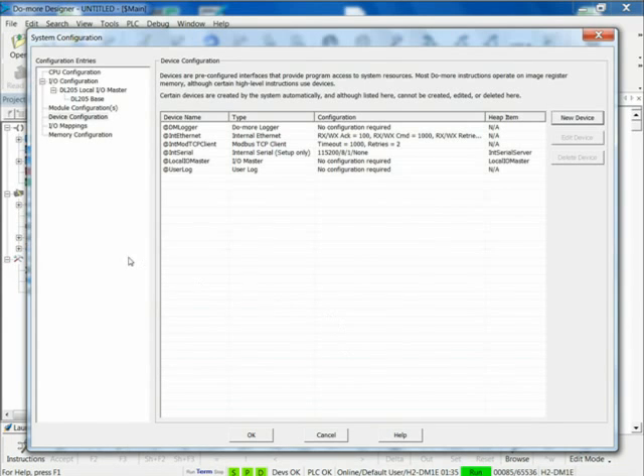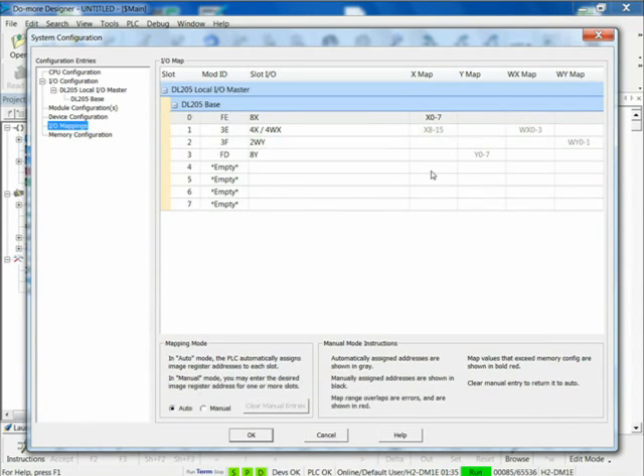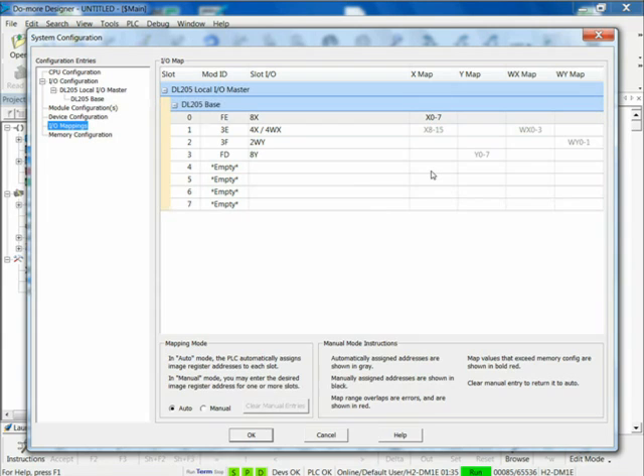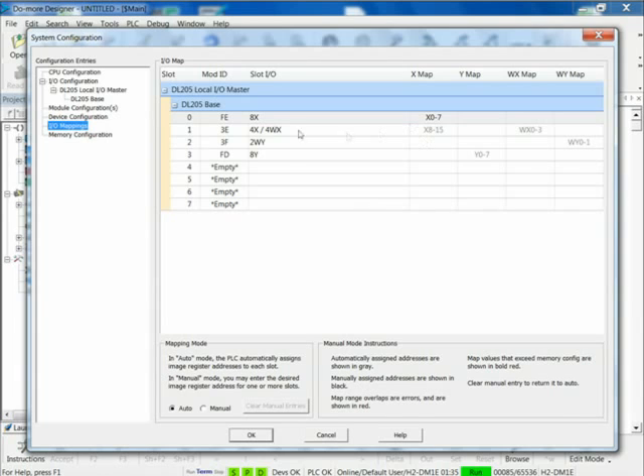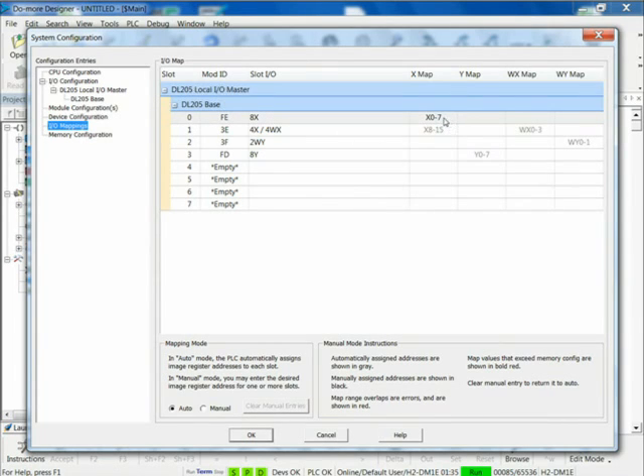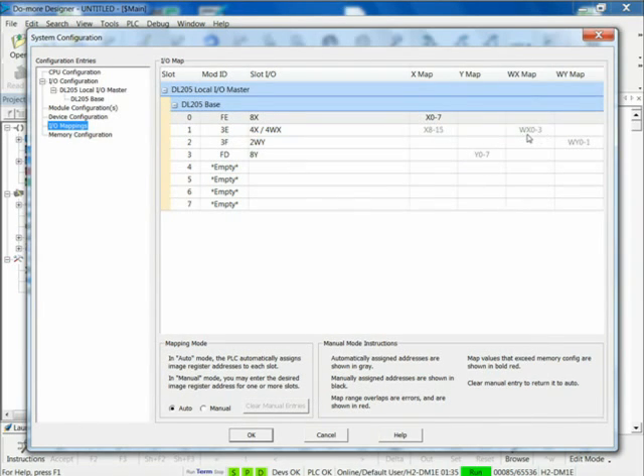What about the I/O Mappings? That just shows you what you have. That shows what the CPU discovered on power-up and what it automatically assigned to the card sitting in the rack. Most people just use automatic addressing. So this just shows you these eight points are showing up as X0 through X7. These next set of points are showing up X8 through X15. And that's an analog card, so it also shows up as WX0 through 3.